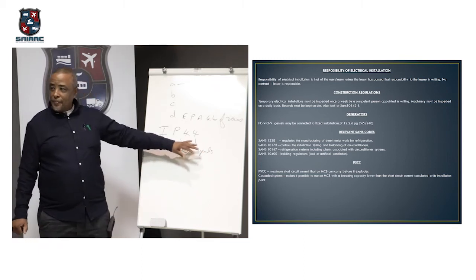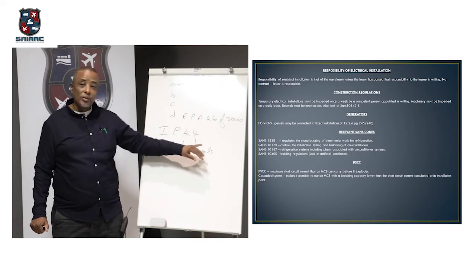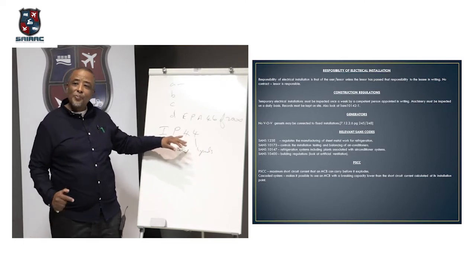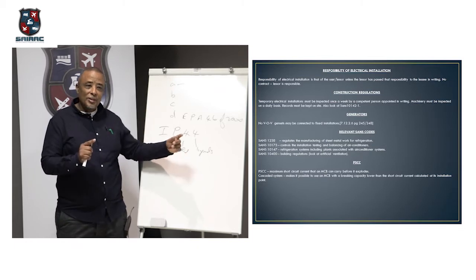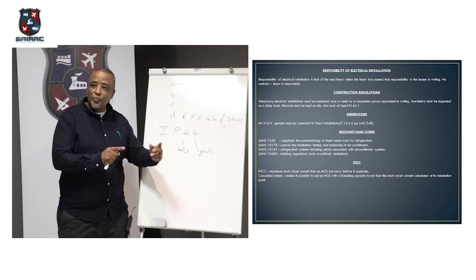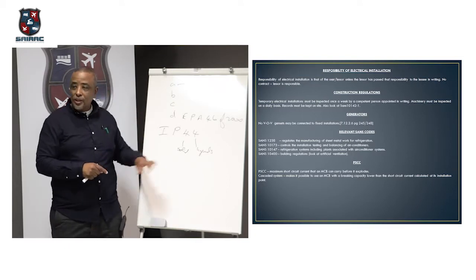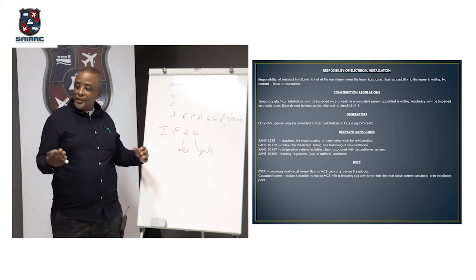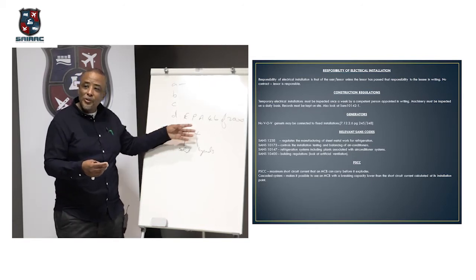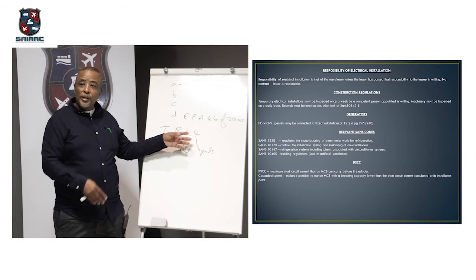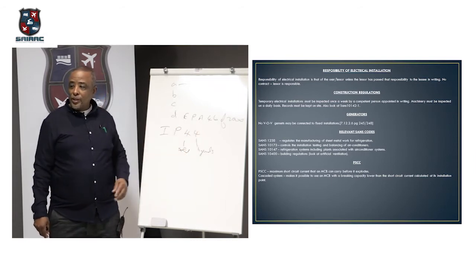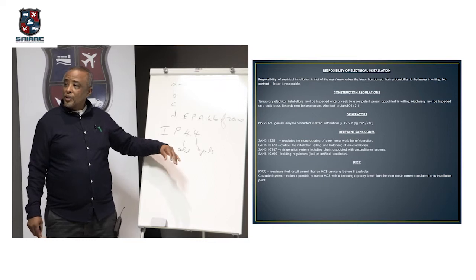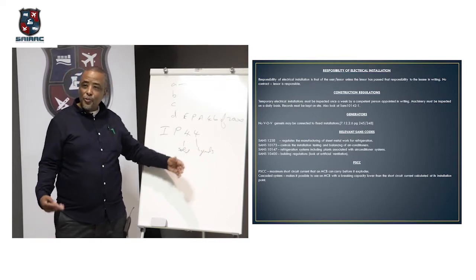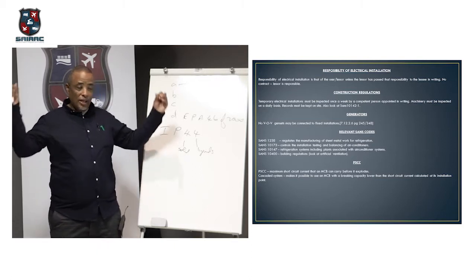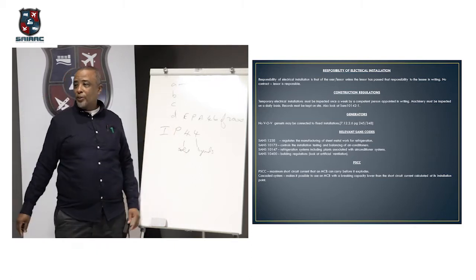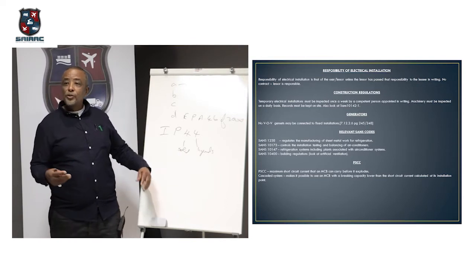If you look at the table, it will tell you what the penetration of the solid is. Standard test finger penetration: how deep must it be before you are able to get to a live part? That's not a solid. Dust: what kind of dust it is, but not combustible dust. Will it be able to get in? How much dust will be able to get in? Liquid, the second one is liquid: what kind of exposure is it to liquid? Is it a slight spray? Is it heavy rain? Is it going to be immersed in water permanently? There is a table that will tell you.